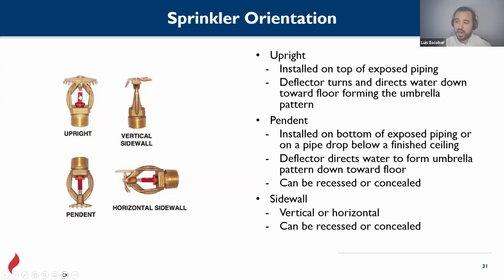So it's going to be oriented upwards, which I used to think the water was released to protect the actual ceiling, but it hits the plate and the water starts falling down with an umbrella pattern. The other one we have is the pendant sprinkler, installed at the bottom of exposed piping or on a pipe drop below finished ceilings. If we have a storage building, for example, the pendant sprinklers could be up high in the ceiling at 22, 25, 30 feet high, but sometimes they can be installed in the offices area, which are 10 feet high most of the time. With these pendant sprinklers, the water is released downwards and hits the plate, and the water is released with an umbrella pattern as well. You can see the curve in the plate. That's what provokes the umbrella pattern.